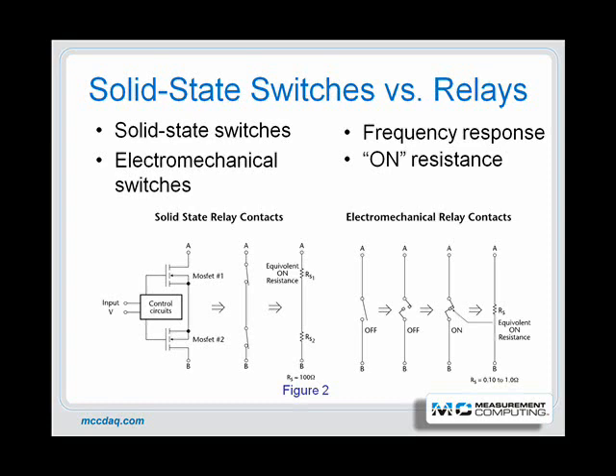Electromechanical relays, for example, are relatively slow — about 1 kHz or less for the fastest reed relays. But they can handle large input voltages, and some can isolate several thousand volts. A relay's size and contact type determine its current carrying capacity. Laboratory instrument relays typically switch up to 3 amps, while industrial applications use larger relays to switch higher currents.